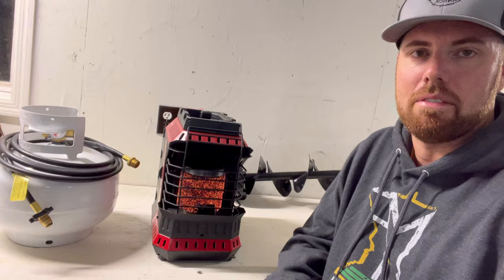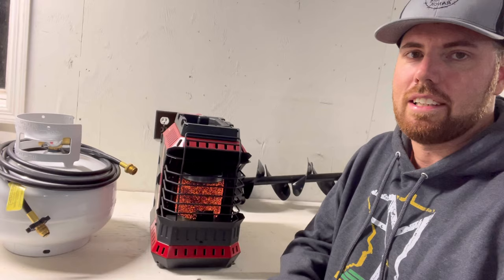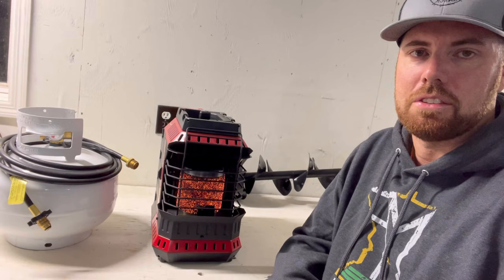Alright, I hope this video helps some of you guys that have been frustrated with the Buddy Flex. Like I said, the first time it happened to me I had this thing totally apart, and then I figured out that once I just cleaned off those two things with a rubbing alcohol pad, it worked good as new again.